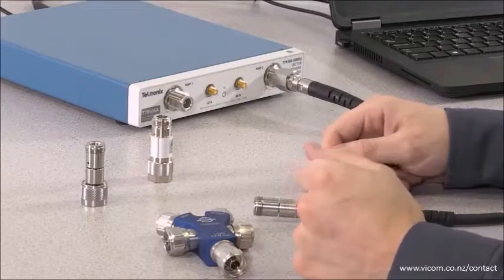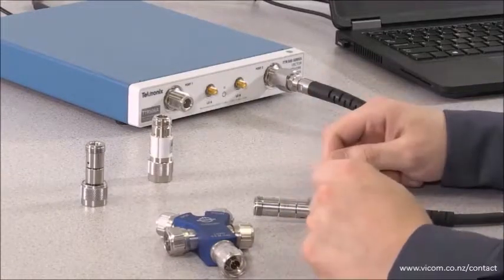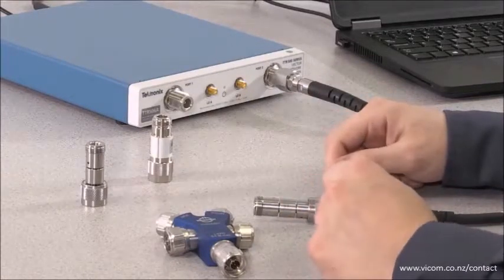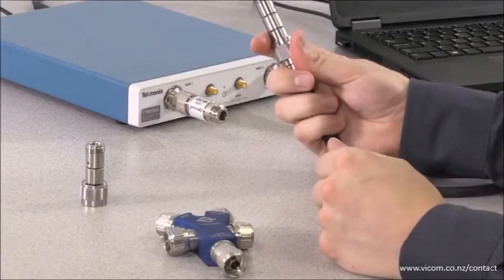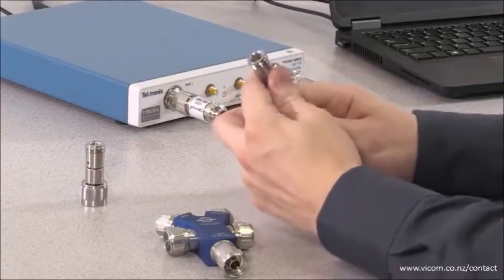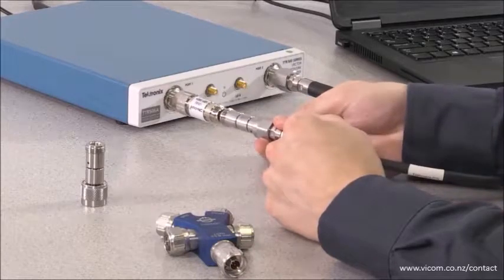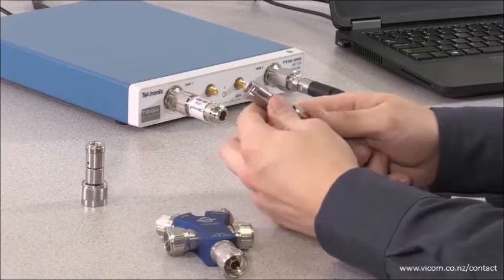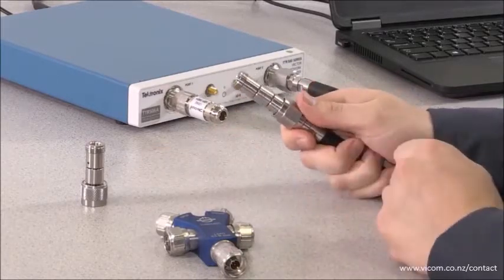So now that we've completed the calibration, let's go ahead and try and connect the DUT up to port 1 of the VNA. But wait, we have a problem. This female-to-female adapter can't connect to the DUT, so we're gonna have to swap it out with the male-to-female version.